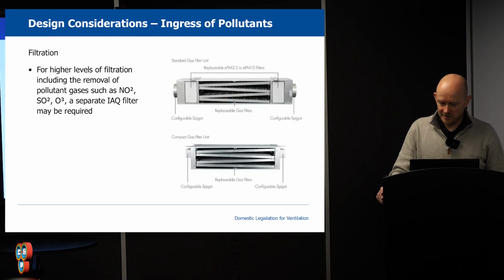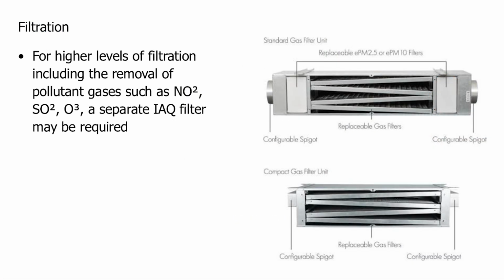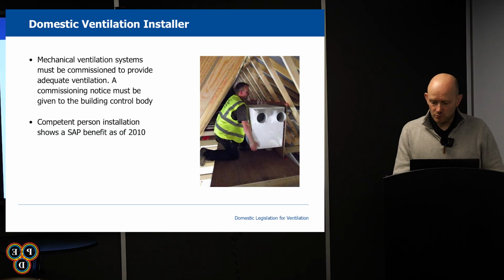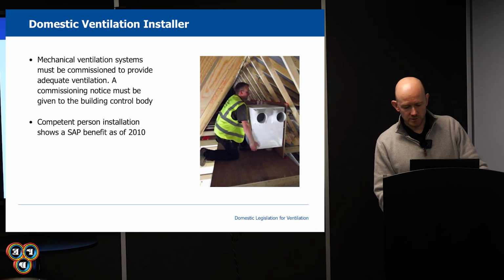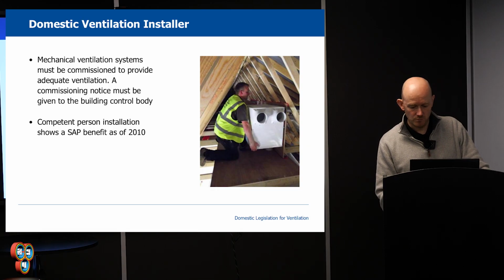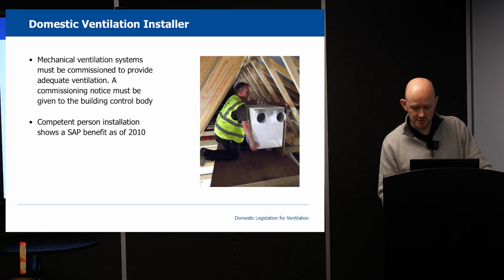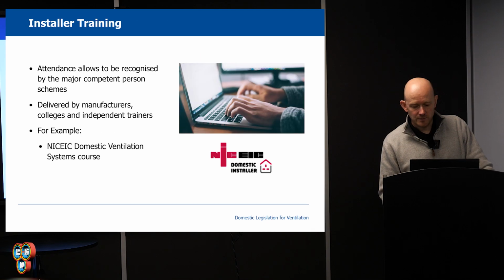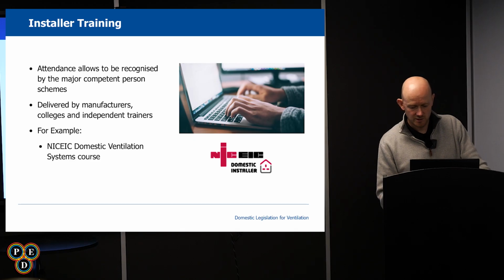NOx filtration may need to be considered on city centre developments or where lower level dwellings are next to busy carriageways, again only applicable to systems that provide supply air rather than background ventilation. It should be noted that adding such filters will add pressure loss to the system, and these filters will need access for routine maintenance. Mechanical ventilation systems must be commissioned by a competent person and notice given to the building control body. There is a SAP benefit when the ventilation system has been installed by a competent person. To become a competent person, you can attend a training course, for example an NICEIC domestic ventilation course, which is delivered by various training suppliers.